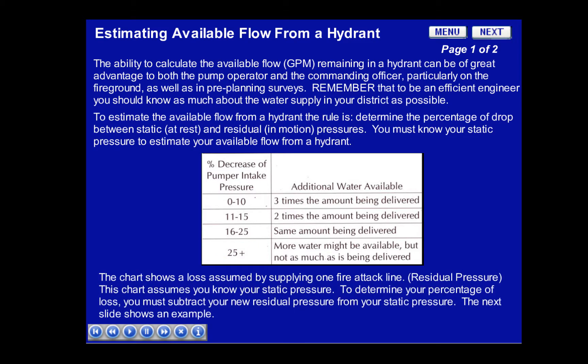The chart shows a loss assumed by supplying one fire attack line, which will mean your residual pressure. This chart assumes you already know your static pressure. To determine your percentage of loss, you must subtract your residual pressure from your original static pressure. The next slide shows an example.